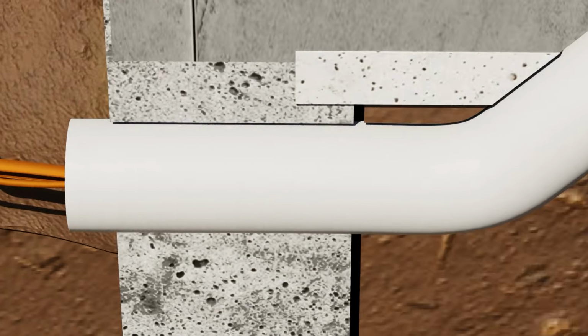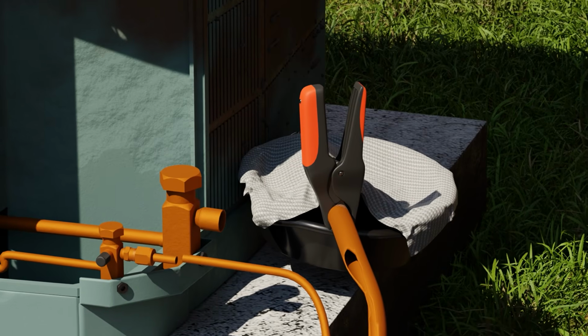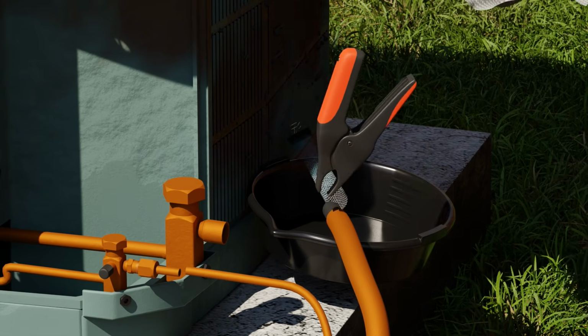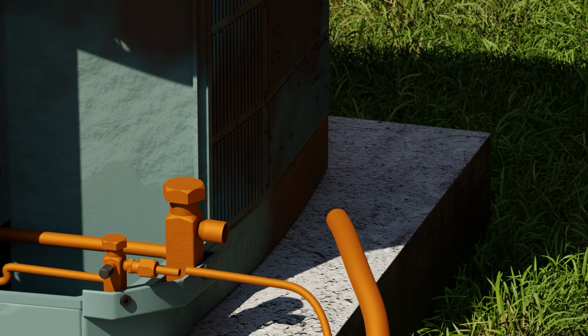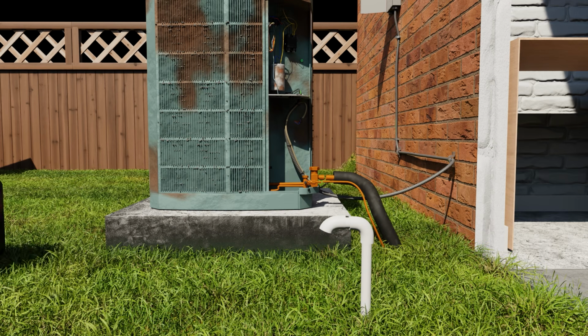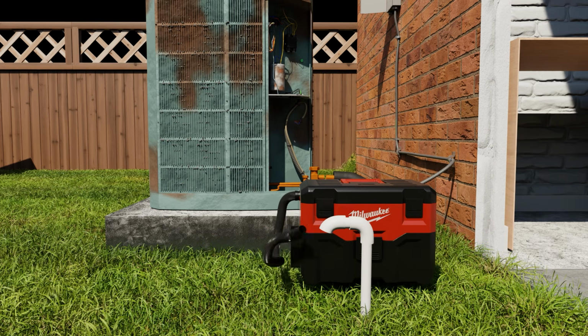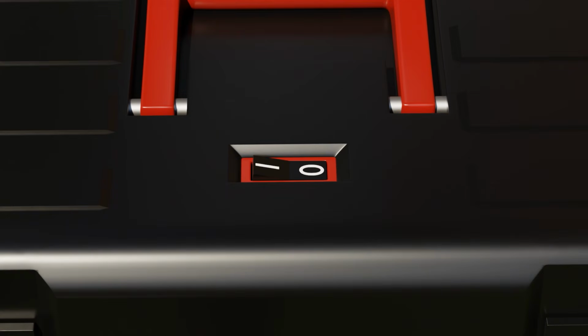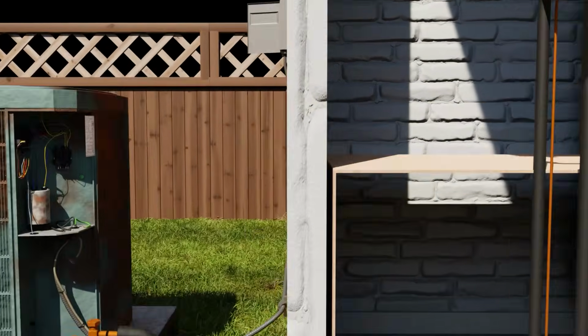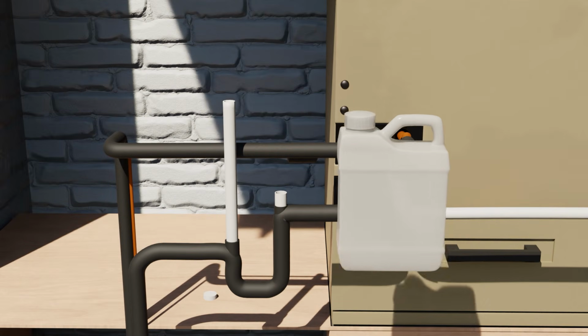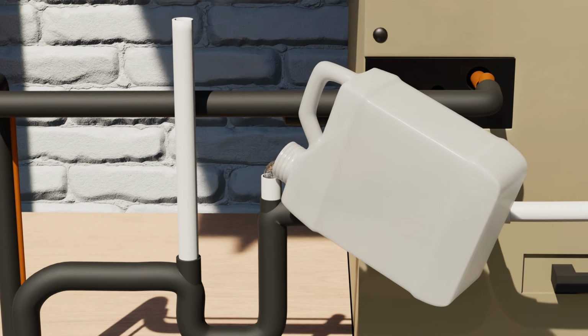Next, if you're going to reuse the drain line, you always need to clean it very well. The best way to clean the drain in this application is by hooking up a shop vac to the outside and running water through it to clean it out. We don't show this here, but you'd also need to put a cap on the vent if this were the application to allow us to draw the water through rather than just pulling air through the vent.